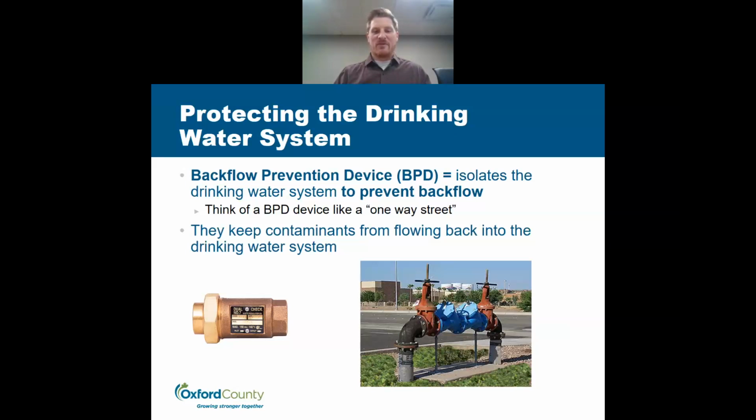Although there are many different types of backflow prevention devices, the general principles are the same. They use mechanical spring-loaded check valves acting against the service pressure, and in some cases, pressure-reducing valves to ensure that if a pressure drop occurs across the device, it will instantly close, stopping the flow of water. Once service side pressure increases above private side pressure, the valves open, allowing flow to resume in the correct direction.